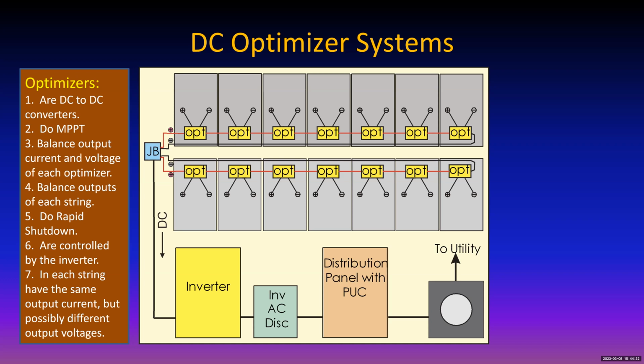But notice the series connections here. The black wires are ground wires. Actually, the DC from the junction box to the inverter consists of a ground wire, and the black is negative, not ground wire. I'm sorry, I made that mistake. That's a bad mistake. But anything that's at more than 0 volts is indicated by a red line there. Each optimizer has a plus and a minus, and they're put in series just like batteries in a flashlight.